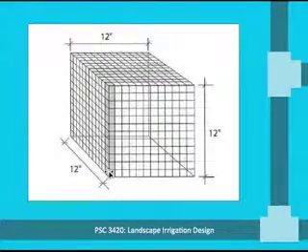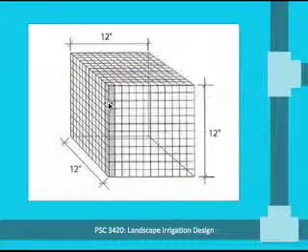So another thing to note here is that the height of the water here is 12 inches or 1 foot, right, for this shaded column. And we know already that it's creating a pressure of 0.433 psi at the base. And that introduces this second way to express pressure, which is known as feet of head. And so at the base of this column, there is 1 foot of head, just at the base of this column.